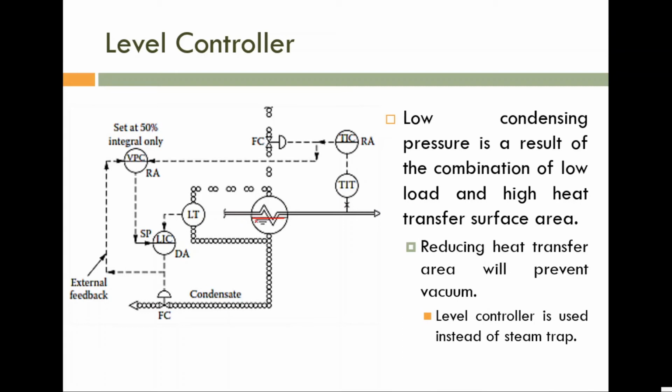A small portion is covered by liquid, means indirectly we are maintaining this liquid level constant. If you are maintaining this liquid level constant, the remaining portion is available for heat transfer. That heat transfer area is fixed. For a time being, assume that this heat transfer area, even if it is partially available, is fixed, because the liquid level inside this steam heater is fixed.